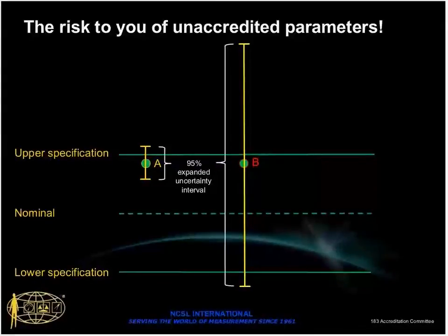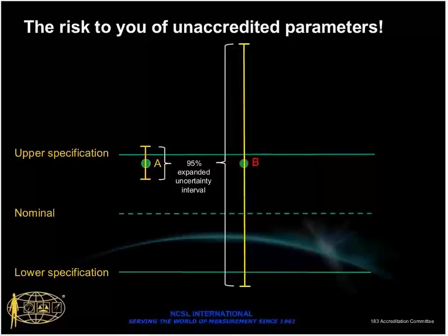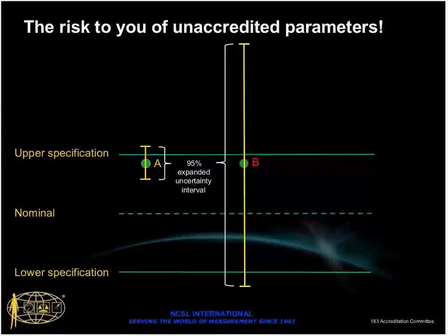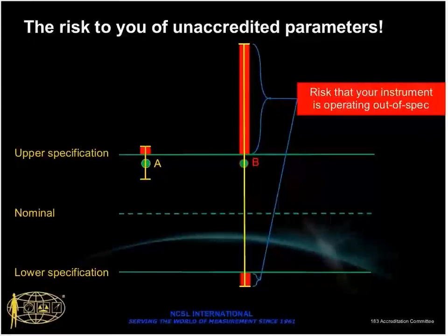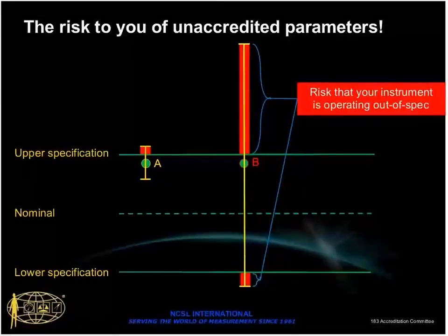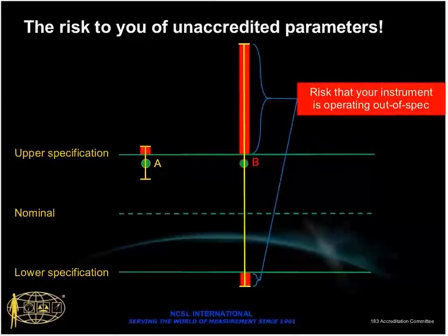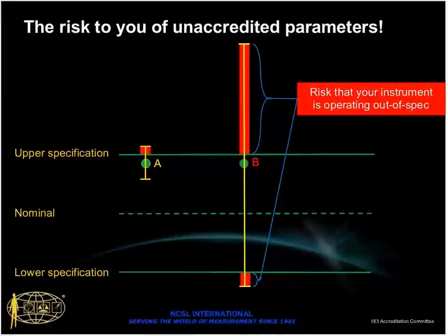And when we look at it this way, we go, okay, so where is the true measurement answer that has no error associated with it? And unfortunately, we don't know where the true answer is. The only thing that we know for sure is the length or the size of the interval of the 95% expanded measurement uncertainty, and that there's a 95% coverage probability that it lies somewhere within there. Well, that's somewhat disconcerting if you realize that any of the areas in red, if that's where the real true answer lies, those represent the risk that your instrument is operating out of spec.